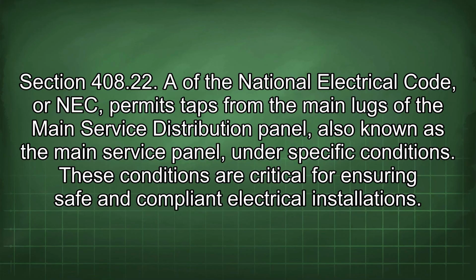Section 408.22 of the National Electrical Code, NEC, permits taps from the main lugs of the main service distribution panel, also known as the main service panel, under specific conditions. These conditions are critical for ensuring safe and compliant electrical installations.